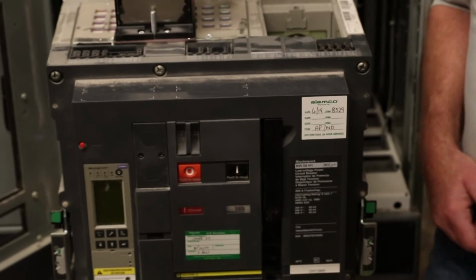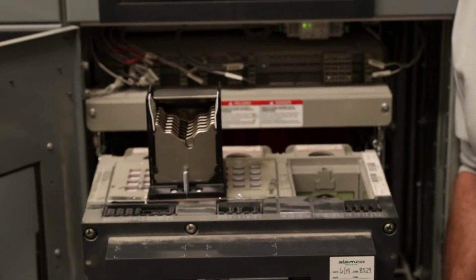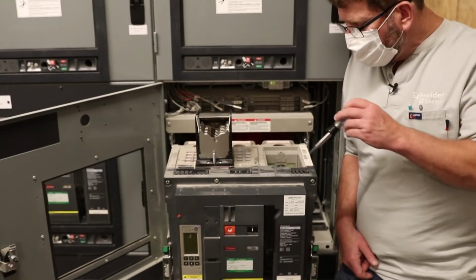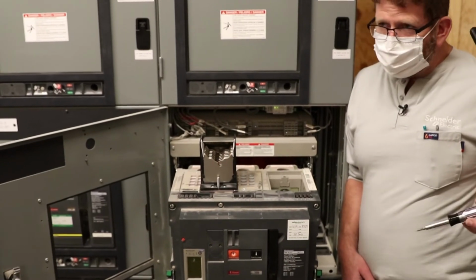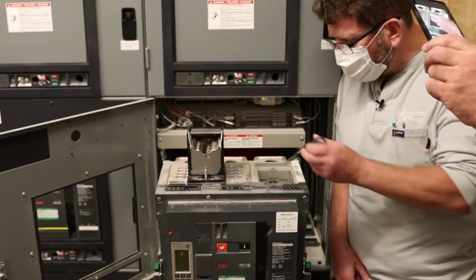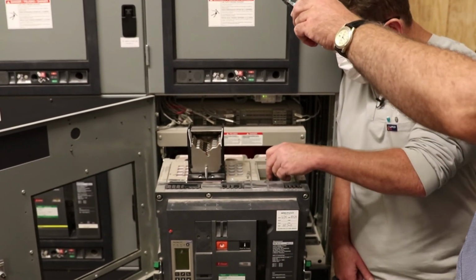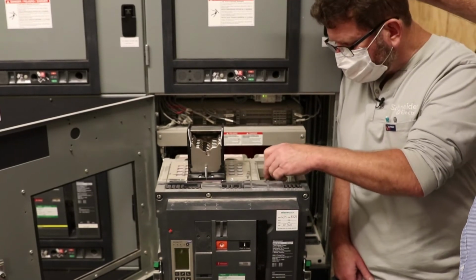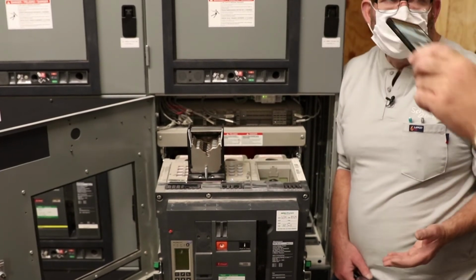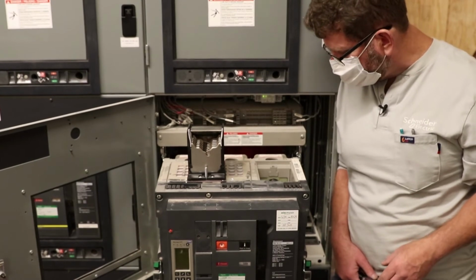There is a wear indicator for these contacts to show you if the contacts have worn. You can't see it now, you have to trust me that it's there. But if the contact's worn, you'll see a little line scribed in the plastic. If that becomes visible, that means your contacts are worn and the breaker needs to be replaced.